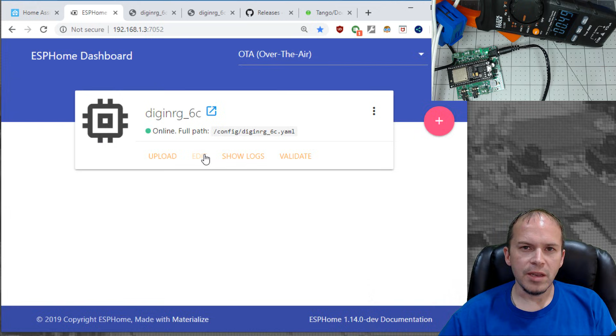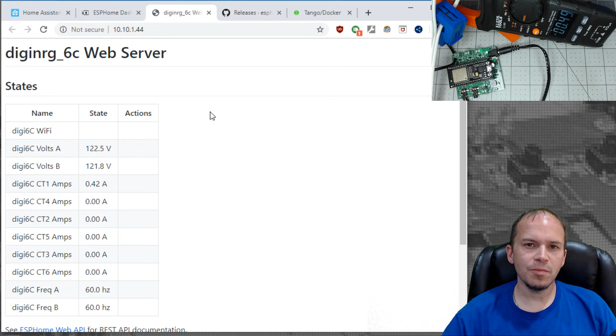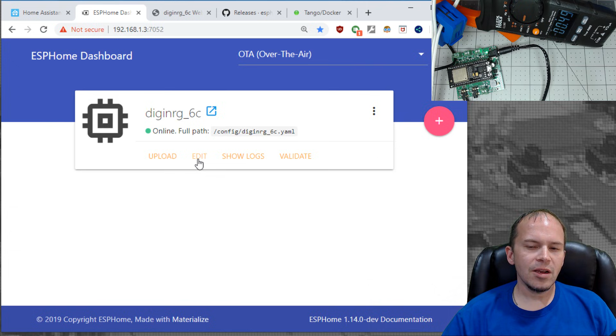Let's do 13,000, and we'll hit save, and we'll hit upload. The compile time should be much shorter because it doesn't have to compile all the libraries just to change that one calibration. Now, if you don't want to go straight into Home Assistant to look for your values, since we did include the web server on the ESP32, you should get a blue little square link that will jump you straight to the web server and show you the different states of the sensors. So we got 0.42. It's pretty close. As you can see, you just keep playing with this number and get it close to what you think is a good value for your clamp.